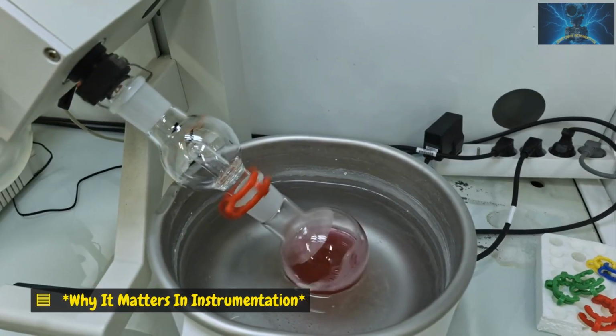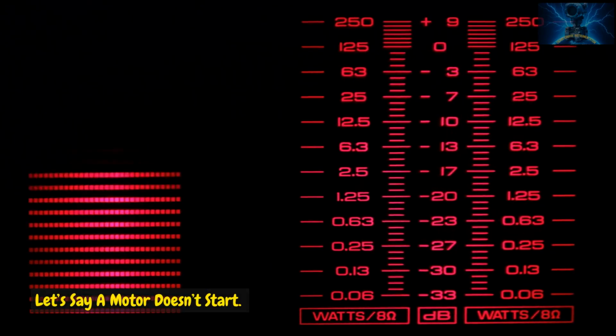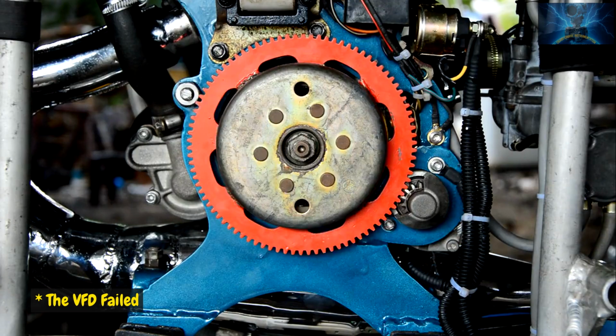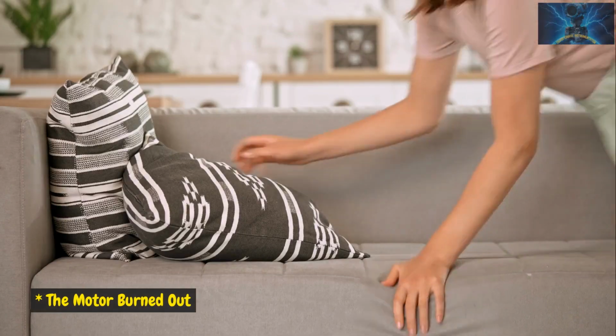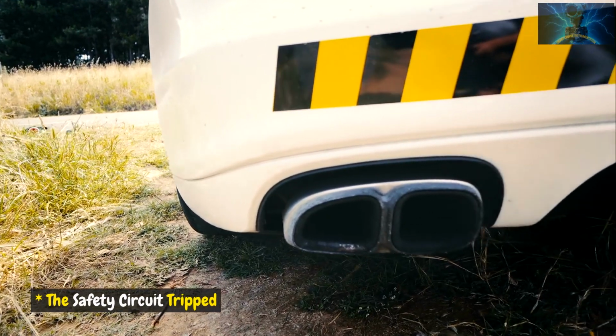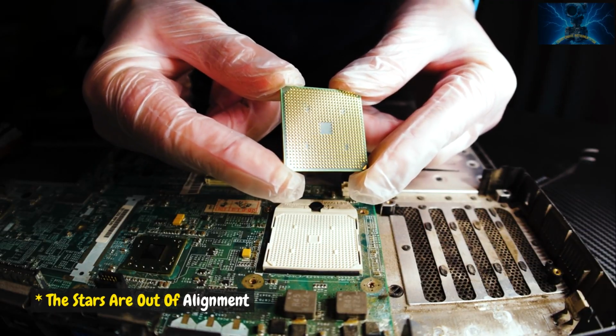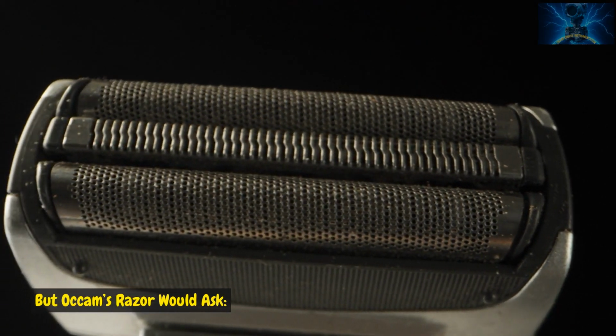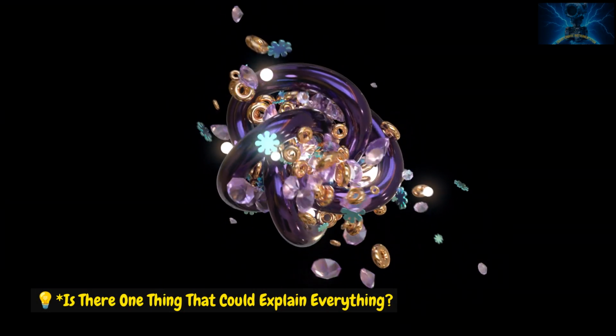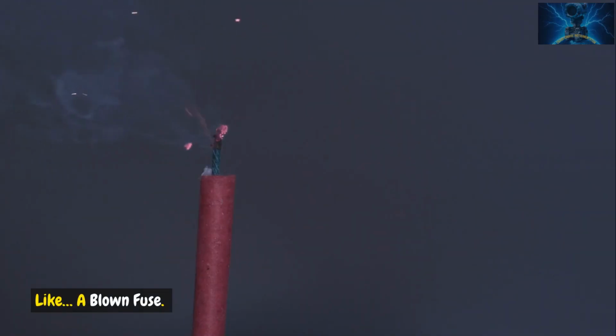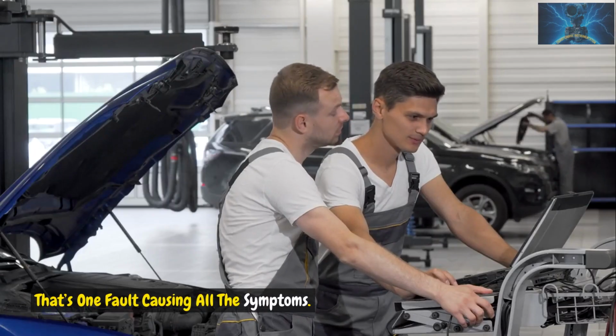Why it matters in instrumentation. Let's say a motor doesn't start. You could think, the PLC is bad, the VFD failed, the motor burned out, the safety circuit tripped, the stars are out of alignment. But Occam's Razor would ask, is there one thing that could explain everything? Like a blown fuse. That's one fault causing all the symptoms.